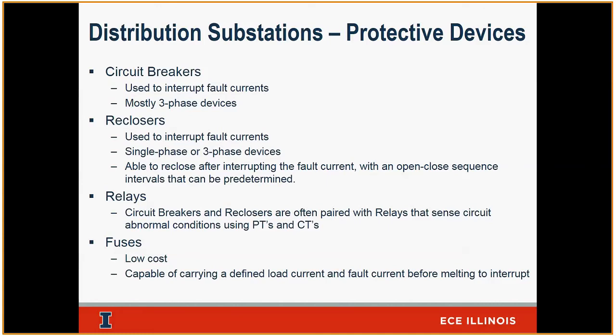Another purpose is you can open it again for what we just described here. So there's no fault, but I need to open and de-energize that line during load current, so the customers are being fed and hot by it. I need to open it during load conditions. I can go ahead and open it. It can handle that amount of current, and it will open. So that's typically what a circuit breaker does in generality. It's a three-phase device most of the time. Again, 99% of circuit breakers that I know are three-phase devices, so they open all phases at the same time.